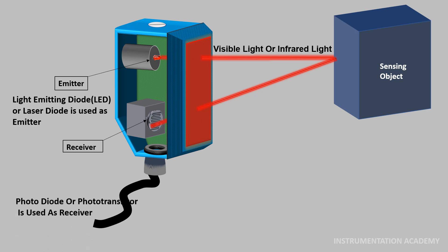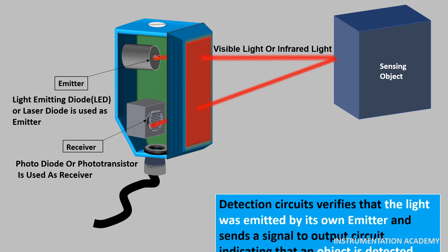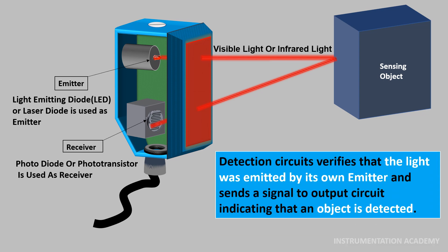The receiver detects the change in light and converts it into an electrical output. Usually, photodiode or phototransistor is used as receiver. The electrical quantity is then amplified by an amplifier and is checked by detection circuits which verifies that the light was emitted by its own emitter and sends a signal to output circuit indicating that an object is detected and triggers an output.